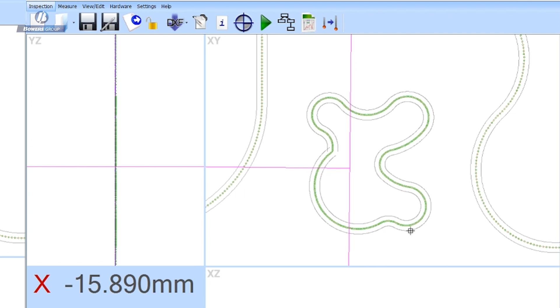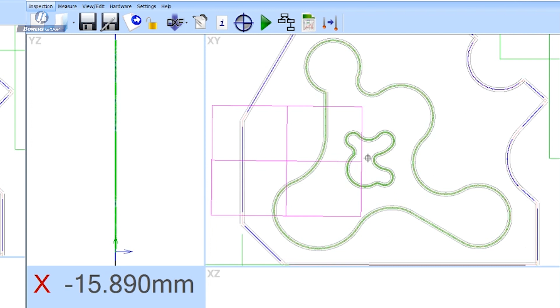And you can see that all of my data points now have gone green and are showing as very close to the nominal line. So visually, I can immediately see that all of those green data points mean that every one of those 2.5 or something thousand data points are within the 0.2 tolerance band that I imported with the DXF. So that is a visual equivalent of the profile projector overlay. Okay, so having brought the DXF in and made a best fit calculation, we get this visual report that all points are in tolerance. That's great.